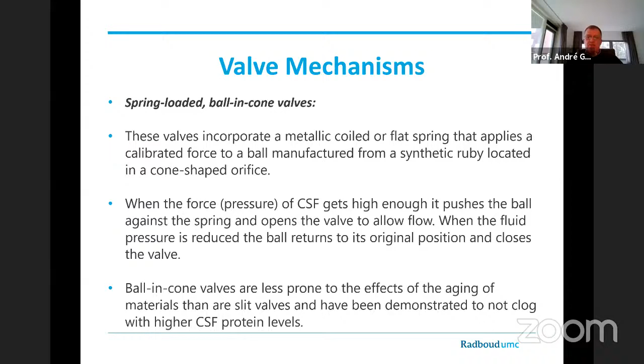And they are still very common because they are not so much a problem with aging of the material. Metal is usually also involved. And the ball and cone and spring system does not have a high tendency to clog, for example, with high protein or with still some red blood cells in the CSF. So they are still very popular valve mechanisms.